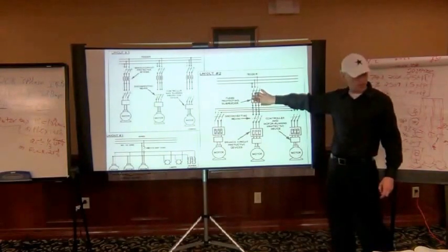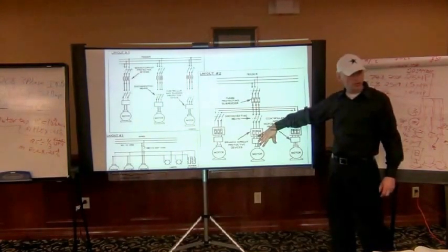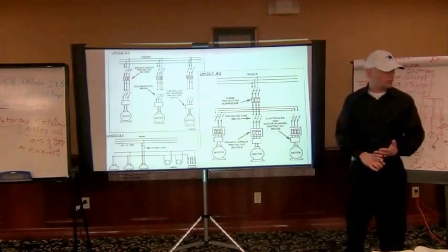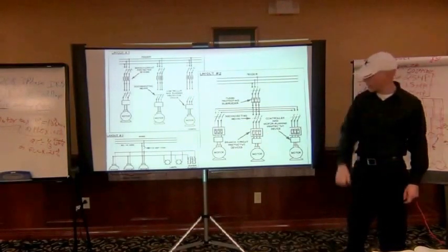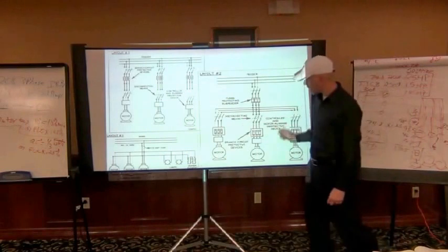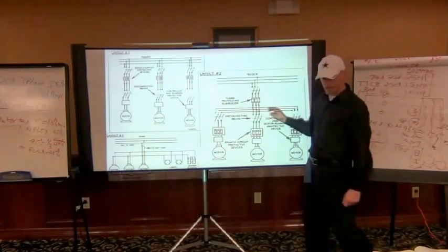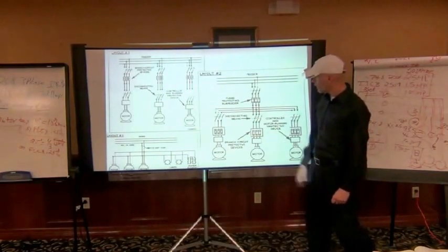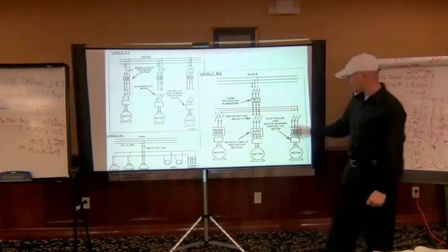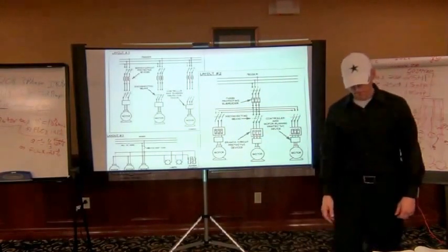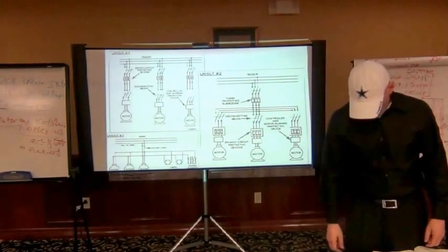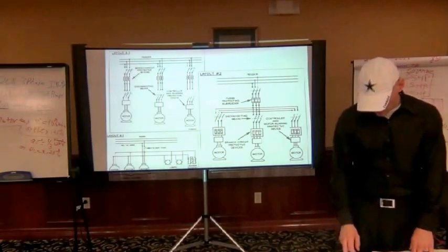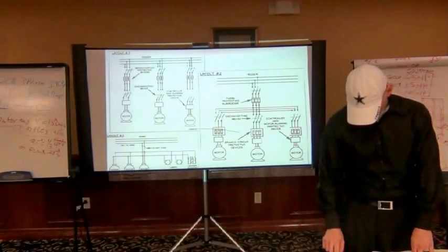And then this set of feeders here, which is just the motor loads, would be the .62, where we do the round up and the round down thing. And then individual motors there. So these feeders here would be sized under .24. These feeders here would be sized under .22. Okay? I think that's pretty much all you need to know on the layout of it.